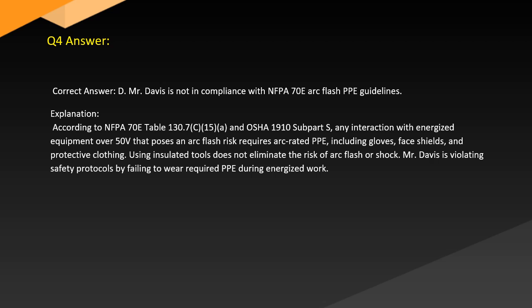Answer. Correct answer. D. Mr. Davis is not in compliance with NFPA 70E arc flash PPE guidelines. Explanation. According to NFPA 70E Table 130.7(C)(15)(A) and OSHA 1910 Subpart S, any interaction with energized equipment over 50 volts that poses an arc flash risk requires arc-rated PPE, including gloves, face shields, and protective clothing. Using insulated tools does not eliminate the arc flash or shock. Mr. Davis is violating safety protocols by failing to wear required PPE during energized work.